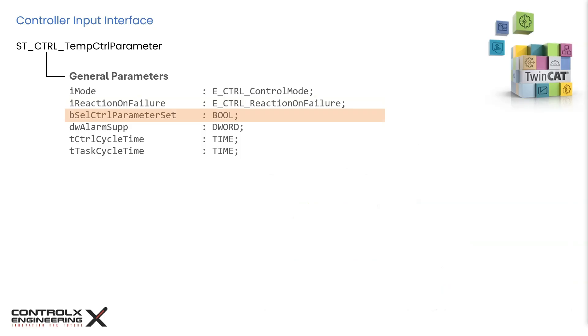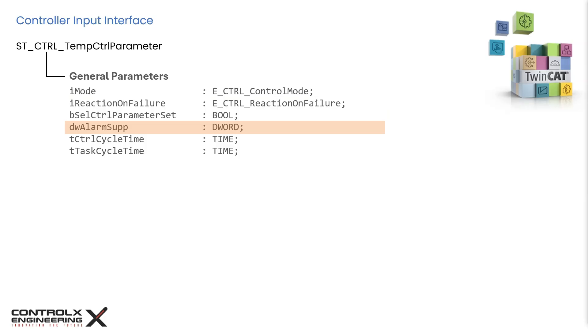This bit allows selection of tuning parameters to the controller. When set to false it will use the internal parameters which are determined by performing a tuning. If you want the controller to use externally provided tuning parameters then set this bit to true. This double word input allows masking of alarms. For example, this mask value is for open temperature sensor alarm.